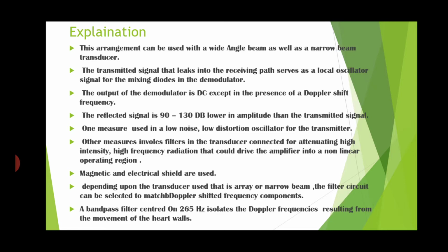Depending upon the transducer used, an array or a broad or narrow beam is used. The filter circuit can be selected to match Doppler shifted frequency components. The bandpass filter centered on 265 Hz isolates the Doppler frequencies resulting from the movement of the heart valves. So using this we can measure the fetal heart rate easily.